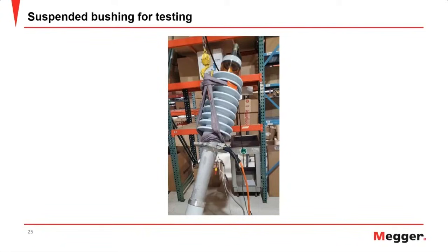So when you are testing a bushing, please make sure that it is suspended and properly secured, so that it's not going to fall and hurt anyone or get damaged in the process. But it is very important that the oil is allowed to recalibrate, readjust, and reset itself within the bushing before performing any tests.